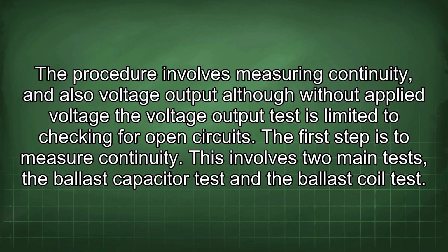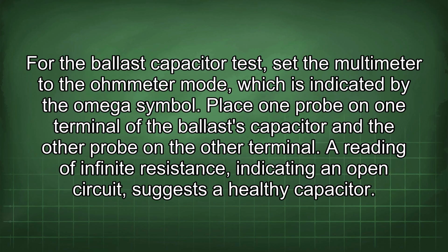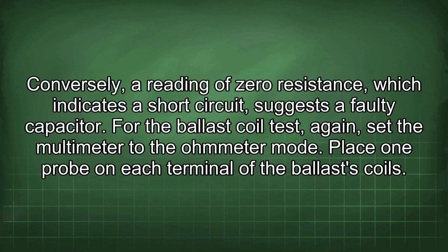The first step is to measure continuity. This involves two main tests: the ballast capacitor test and the ballast coil test. For the ballast capacitor test, set the multimeter to the ohmmeter mode, which is indicated by the omega symbol. Place one probe on one terminal of the ballast capacitor and the other probe on the other terminal. A reading of infinite resistance, indicating an open circuit, suggests a healthy capacitor. Conversely, a reading of zero resistance, which indicates a short circuit, suggests a faulty capacitor.